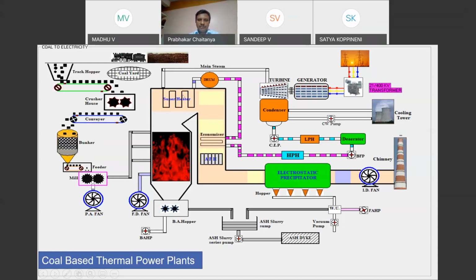And there is one more thing. This drum will be at a very high pressure, around 180 kg per centimeter square. It's a sort of small reservoir. If a sudden urgent requirement of load arises, the steam flow going into the turbine is regulated by a valve. I have not shown it in the figure. There will be a turbine control valve, which will regulate the amount of steam flow going into the turbine. For momentary purposes, if we open the turbine valve more, more steam will flow into the turbine, and the generation capacity will be on the higher side. But it is only for a momentary time, because as long as the feeder speed is fixed, we cannot have a higher steam flow just by opening the valves.